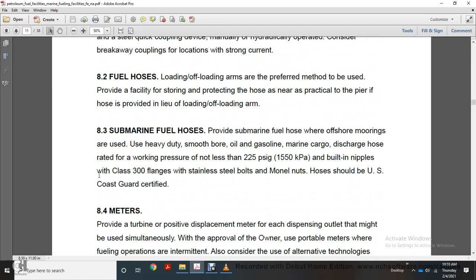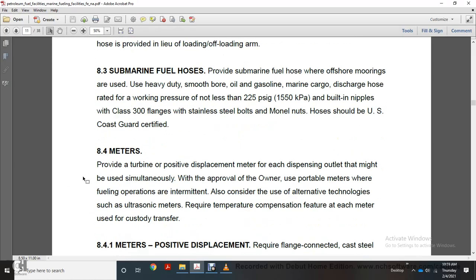Submarine fuel hoses. Provided with a submarine fuel hose with offshore moorings, used with a heavy-duty smooth bore oil, gasoline, marine cargo discharge hose rated with a working pressure not less than 225 psi gauge. Built-in nipples, classes of 300 flanges with stainless steel bolts, Monel nuts, and hoses should be used as Coast Guard certified. 8.4 meters. Provide turbine or positive displacement meter with each with a dispensing outlet with a might be used simultaneously with the approval of the owner.